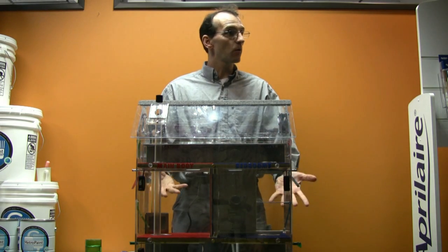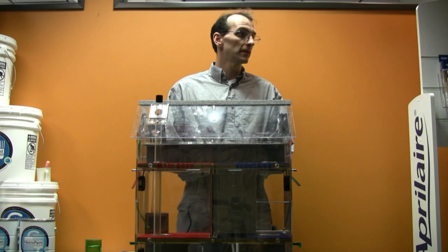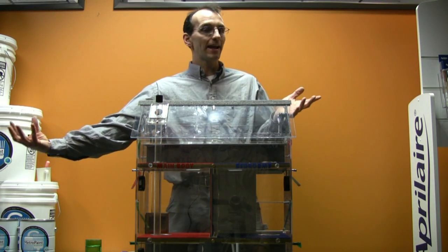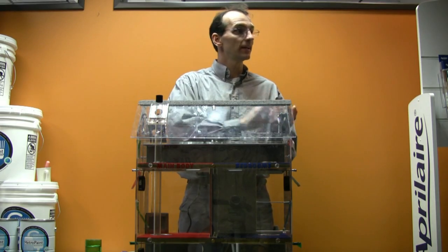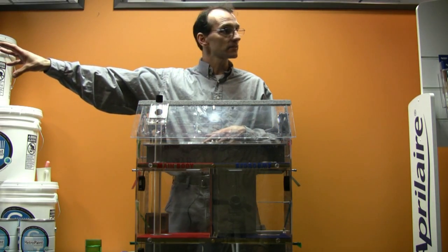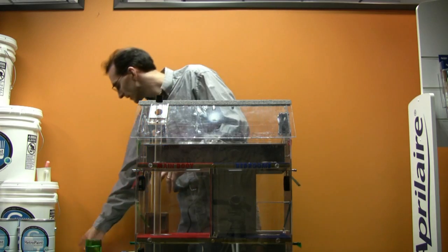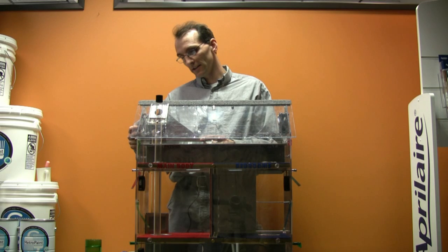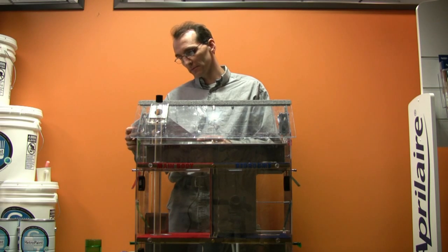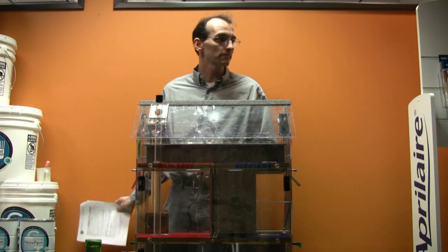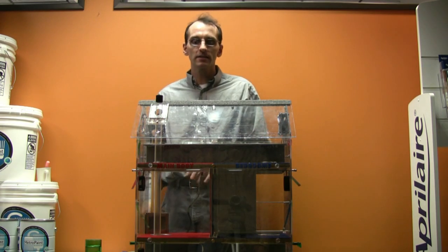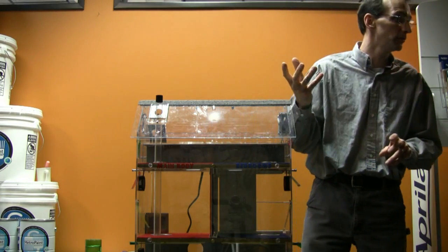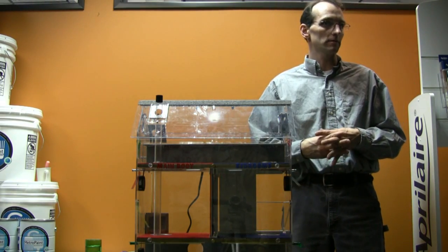Now, if that water heater wasn't your standard open draft water heater, but a high efficiency direct vent water heater that brings its own air in from the outside for combustion and then puts the exhaust air back outside, you have different parameters. For that, they don't even want you to think there could potentially be a problem until you're at minus 15 pascals. And you could take a standard one, and if you can adapt that to be a power assist draft unit, you could also get to the minus 15 pascals.